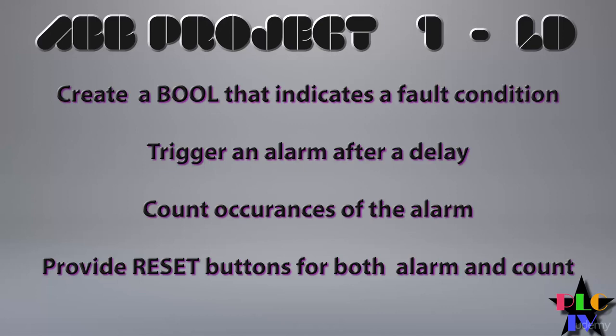So we're going to use a digital alarm. That's going to be something like a low-low switch or a high-high switch, or if you're feeling ambitious, you could do one of each. But we want at least one digital input, which is going to create an alarm. Now that doesn't actually have to be mapped to a physical input. We're just going to use a bool — a memory register, a variable from our database. And after a time delay, give it something like five seconds, we're going to then trigger an alarm. We don't need to do alarm and notification bits — just an alarm bit and then a single alarm reset to reset the condition.